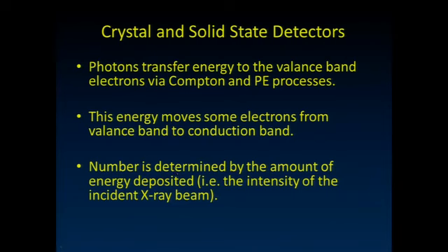That electron may immediately fall back down into its valence band and give off a little bit of electromagnetic energy in the visible light range. Things that do that immediately, that return immediately and give that light off, are called scintillators. And things which take a little bit more time to do that are called phosphors. So scintillators and phosphors are very similar things.